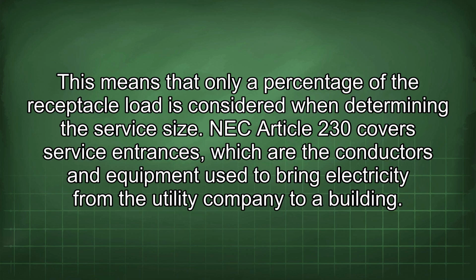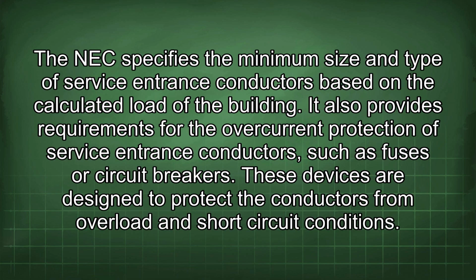NEC Article 230 covers service entrances, which are the conductors and equipment used to bring electricity from the utility company to a building. The NEC specifies the minimum size and type of service entrance conductors based on the calculated load of the building. It also provides requirements for the overcurrent protection of service entrance conductors, such as fuses or circuit breakers. These devices are designed to protect the conductors from overload and short-circuit conditions.